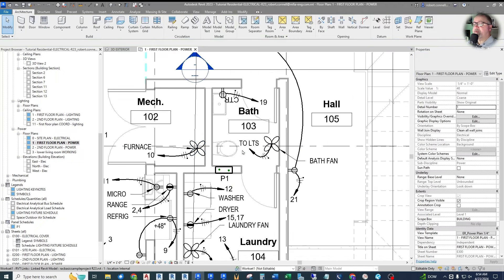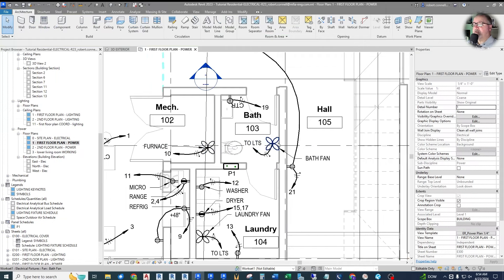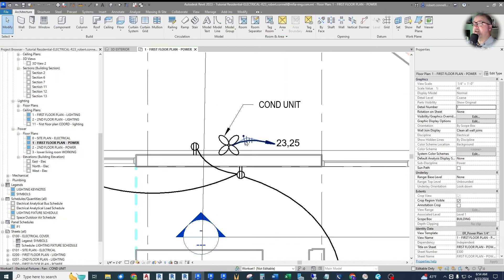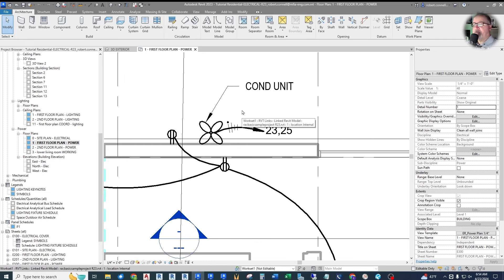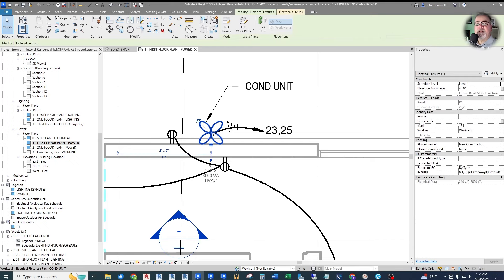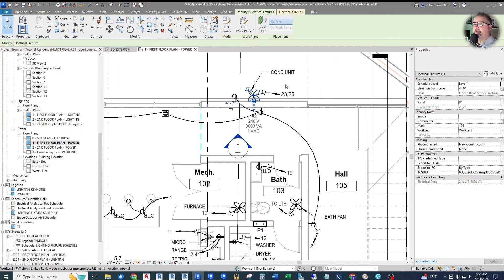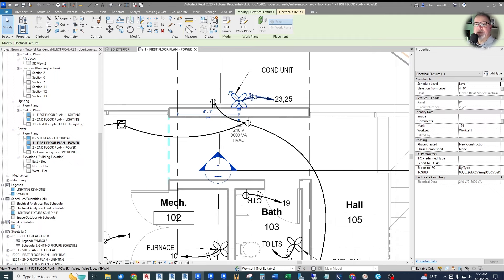That works on a small project. The circuiting is shown here — this one shows that it goes to the lights, and we have an exterior condensing unit circuiting shown here. In actual commercial work, a lot of firms like to go a little further and give more details: how many horsepower is the piece of equipment, what voltage is it at, what's the maximum overcurrent protection required, what size feeder should it have if it's larger than a number 12. Those kind of details we will often put in a separate schedule.